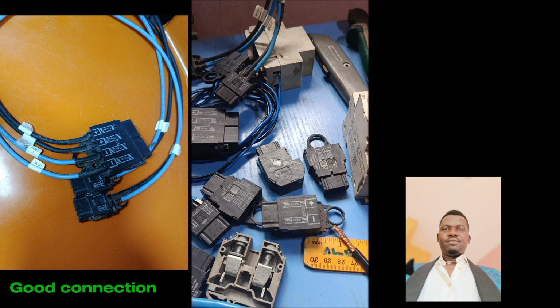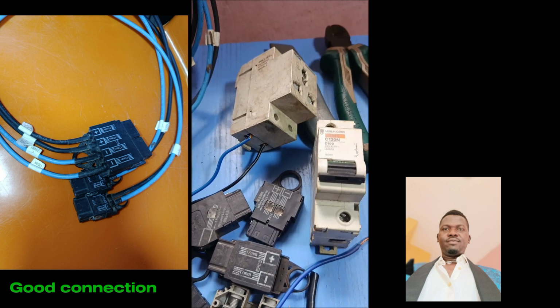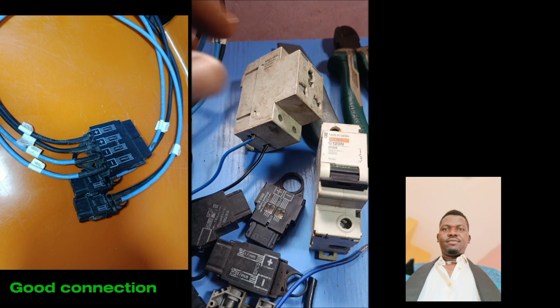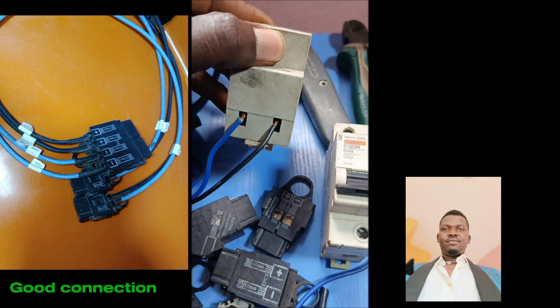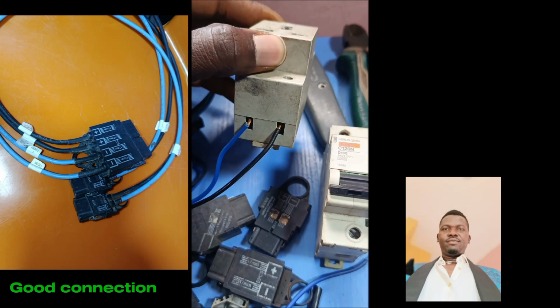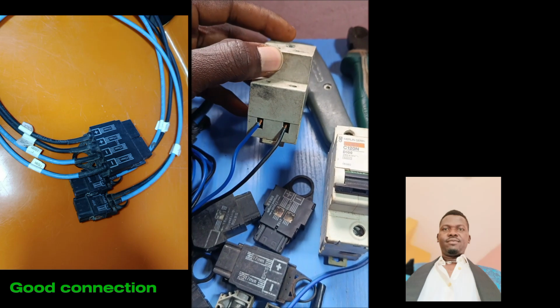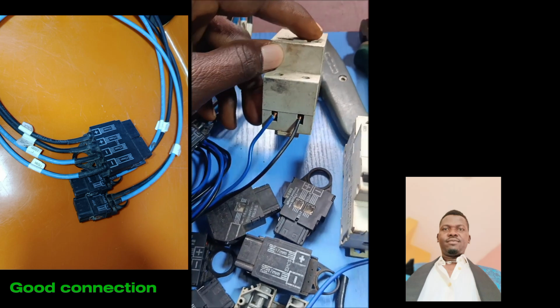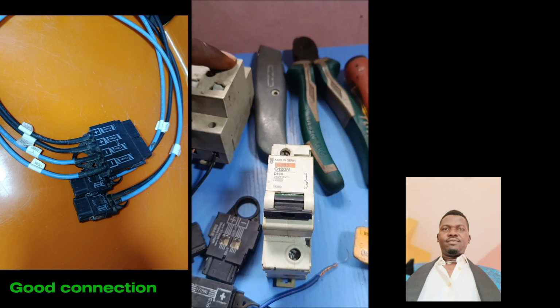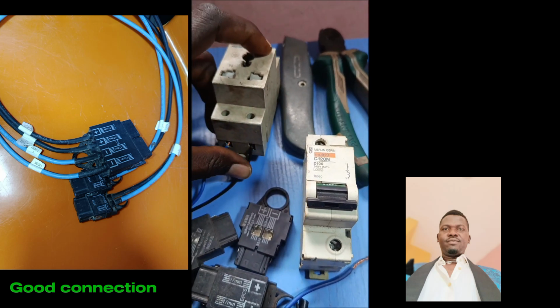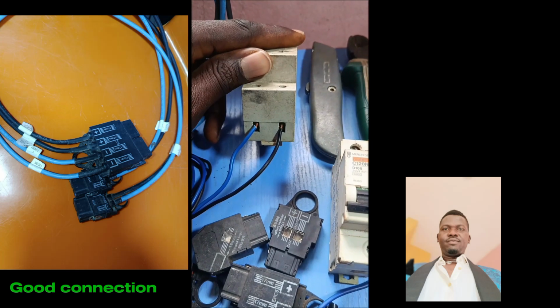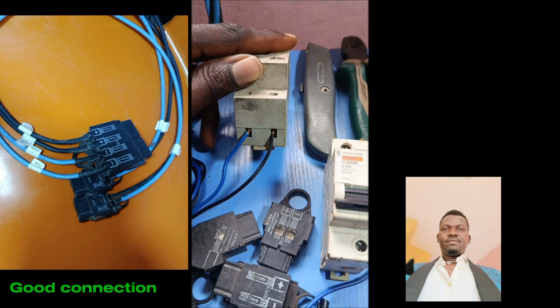Also, when I said stripping too long, this is typically what I mean. See, this connection is not good enough at all. If by any mistake a metal device touches these two, there will be a problem. Boom.